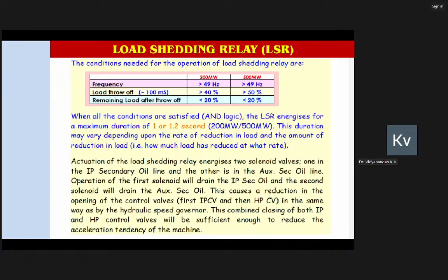It is actually depending on the second signal, that is, how much megawatt is reduced within what period. And that will decide how long the load shedding relay will remain in service. The basic purpose of this load shedding relay is to prevent the chances of overspeeding of the machine in case of sudden unloading.